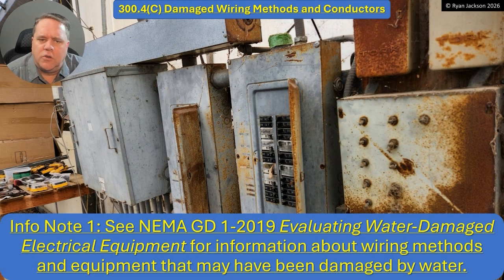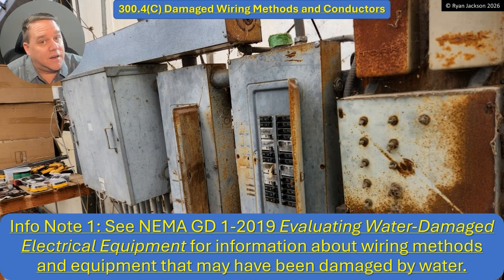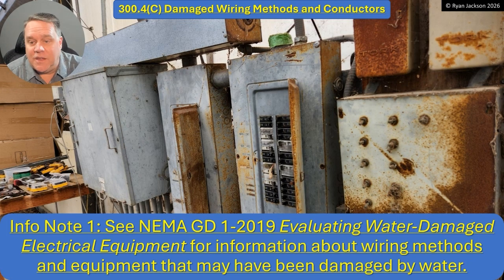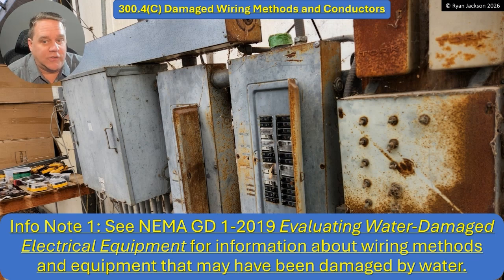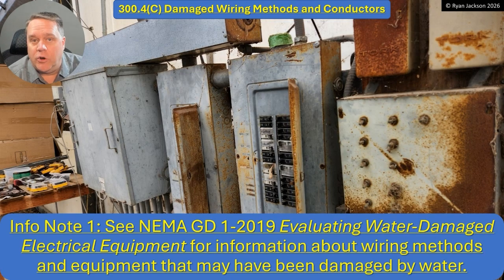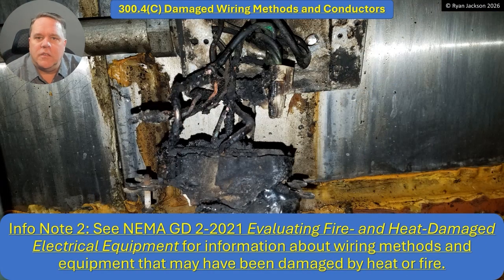Looking at this picture here, we've got an indoor plant growing operation — just flowers and such — and you can see they used regular old indoor equipment. Eventually that equipment is going to look like this and then even worse. At what point does it need to be replaced? Somebody's got to make that call — ultimately the AHJ, although hopefully the owner will pull the trigger before the AHJ even gets involved.